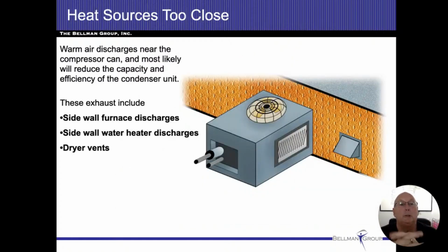Warm air discharges near the compressor can most likely reduce the capacity and efficiency. So, sidewall furnaces, sidewall water heater discharges, and dryer vents. Now, the furnace, sidewall furnace discharges, I mean, the furnace and the air conditioner are not going to be running at the same time. And if they are, they might be two separate units. So because of efficiency, I can't buy into that one.